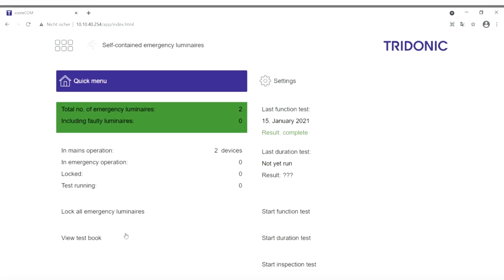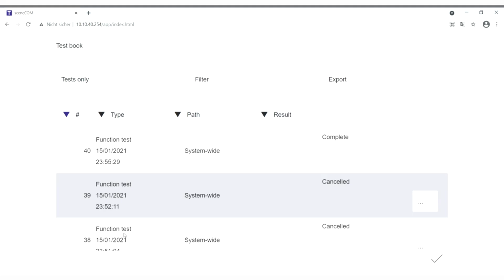What we can also do is have a look at the test book. It's a requirement that all of your tests are recorded and stored, and the SceneCom does that for you automatically. Here you see the last test carried out, our manual test, a system-wide test, and we see that it was completed. You also have the option to export the test in either PDF or XML format, which you can then store locally on your PC.